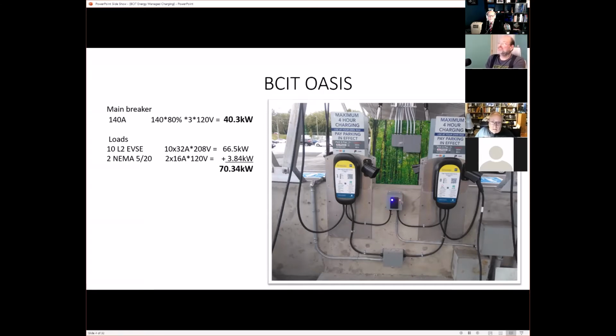So we had to control the charging rates of the cars so that we would never exceed the 40 kilowatts. Overall, there's also limits on each line because it's a 3-phase system, so it's 112 amps per line in the panel that we also have to limit.